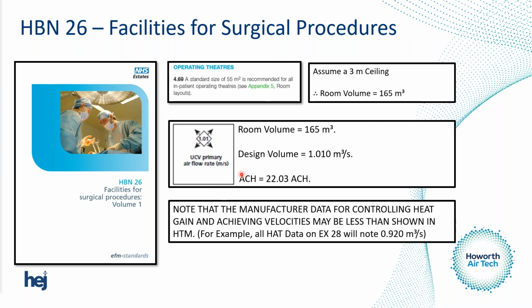Speaking from my own shoes, our Xflow 28 has a minimum design flow rate of 0.92, 920 litres. That's important to know because if you do the HBN 26 design, with your 55 metres squared and 3 metre ceiling, then drop our canopy in and put in the design flow rate to the canopy from the manufacturer, you're going to be under your design air change rate. The reason we give you this design air change rate is that we've taken account of all the heat gains inside the canopy, considering sensible and latent heat gains that come from the motors and the lighting. With 11 degrees off coil, that will give you something like 18, 19 degrees within the operating theatre. So this is a design flow rate for a building services application.